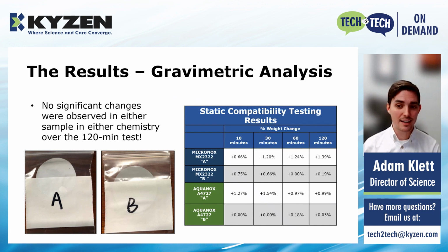And again, if we look at the data, there's very little change at all. Most of them are less than 1%. And for the ones that are greater than 1% change, they're not much greater. So this is good news to us because it indicates that these materials show good compatibility with both of the cleaning chemistries that were tested.